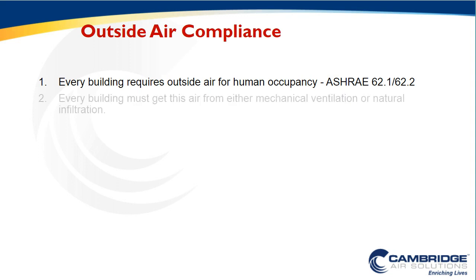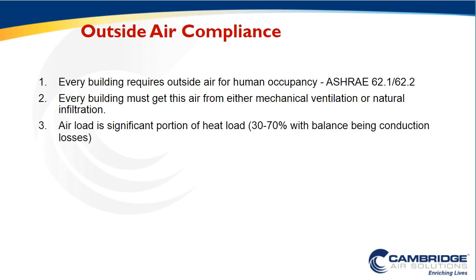Secondly, these buildings must get this air either from natural infiltration or mechanical ventilation. Many codes across the country have come a long way in the last 5 years to making sure that we actually need mechanical ventilation, and very few, I would say, building standards allow us to use all natural infiltration to meet an outside air requirement. But ultimately, we know that all buildings need to breathe in order to allow fresh air for the occupants inside the space.